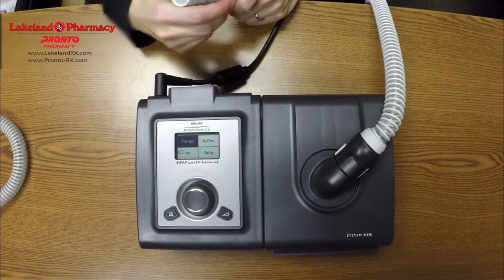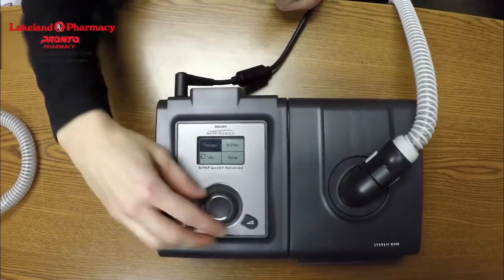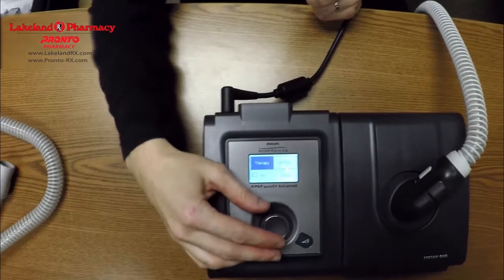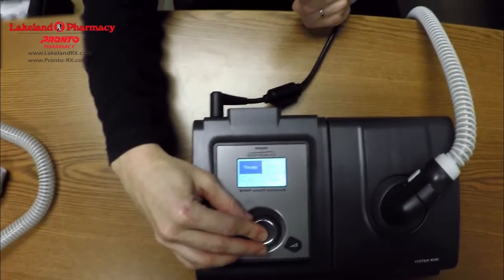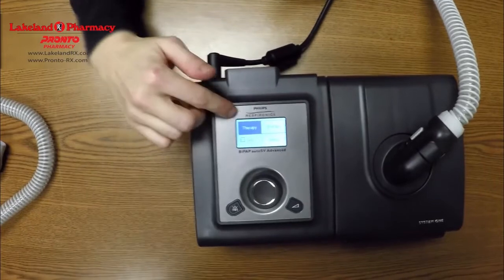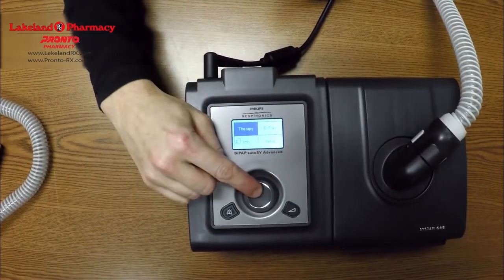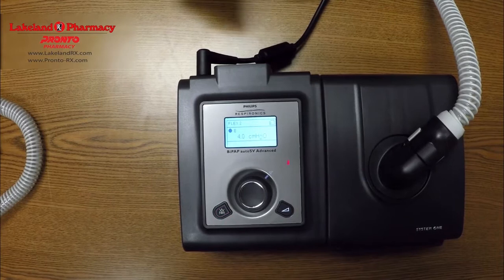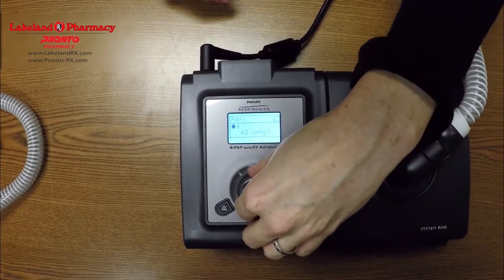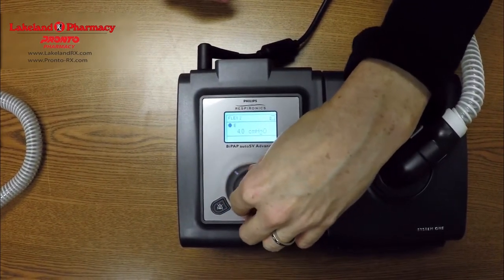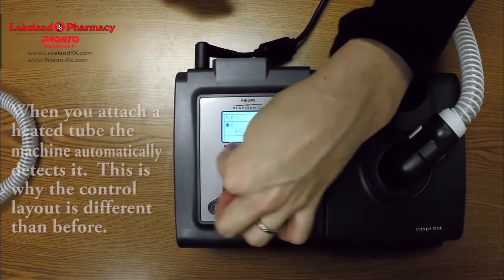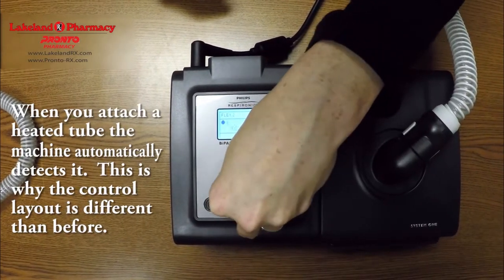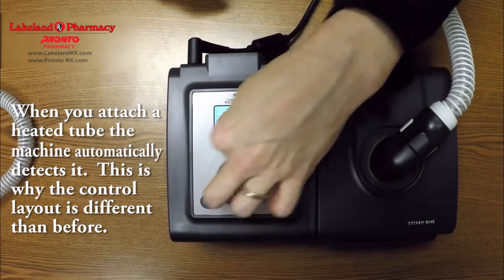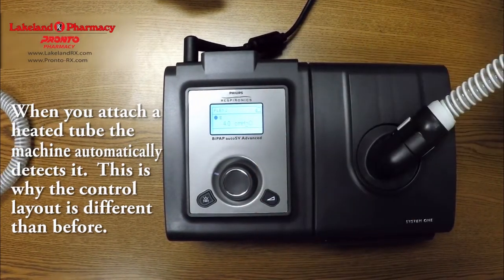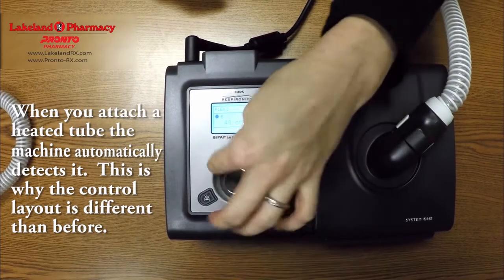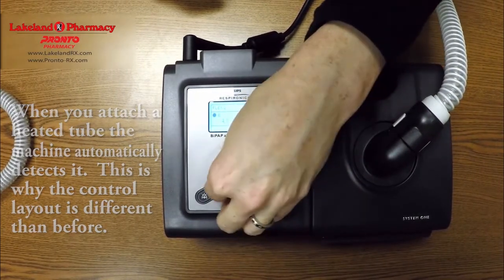In order to adjust the heated tubing setting, it's different from how we were adjusting earlier with the humidity, so I'm going to go through that with you. You're going to go into the therapy again, like you did before. Before, this is how you would adjust the humidity, that's how much water or moisture you would actually get. This will now regulate how hot the tube actually gets. So the higher this number, the hotter this hose will get. If you want it on cool, put it on 0. 1 through 5 is your heated settings.